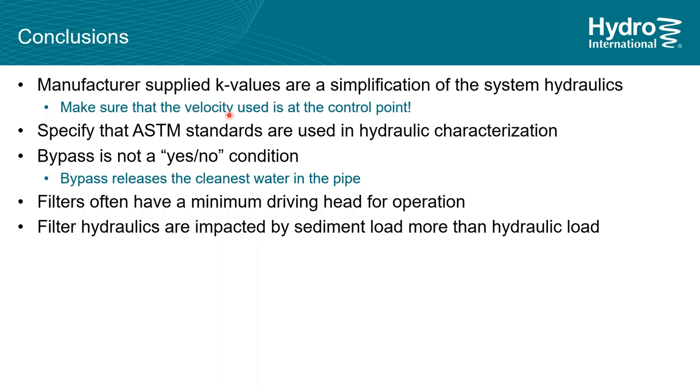But if you have some extra space on site and you just want to get a rough idea, this is a real convenient way to do it. If you want a real clear picture of your hydraulics, you can always specify ASTM standards, that the system be tested to those, and that's a good general bedrock test you can run. Bypass is not some kind of binary yes/no thing. It is kind of a switch that goes slowly from full treatment to increased bypass. It bypasses the cleanest water in the pipe first, so that could be useful for you.